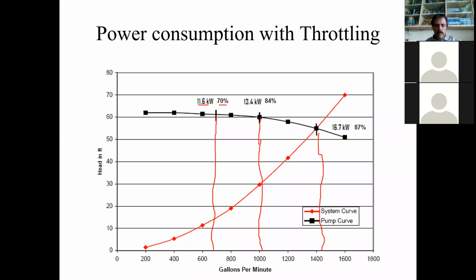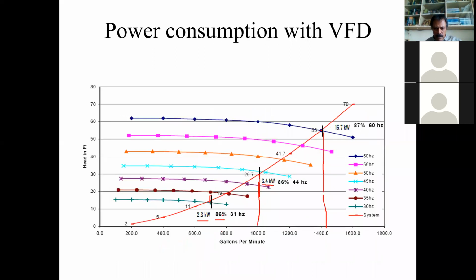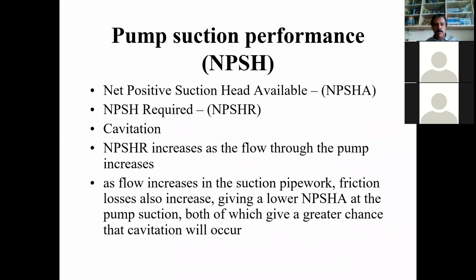So you can see the difference which the VFD is able to accomplish. Efficiency also: here it is 70%, here it is 86%. So with the VFD, the advantage is that the efficiency more or less remains the same. It doesn't affect the efficiency.